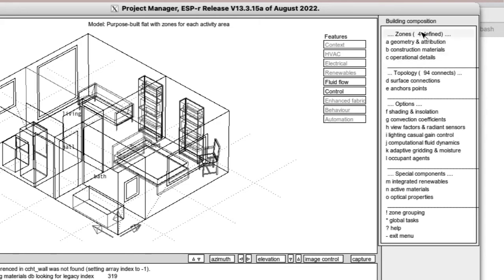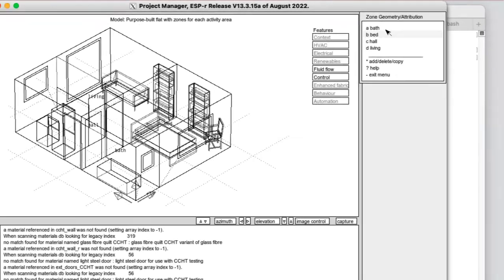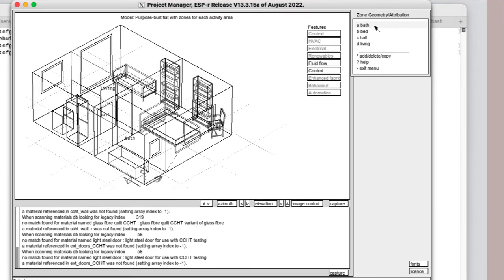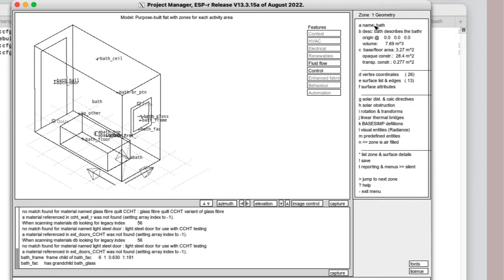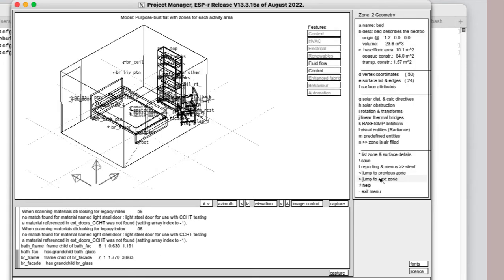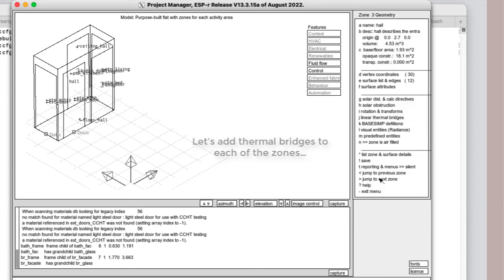The usual suspects for thermal bridges are where the concrete floor structure meets the facade, where internal partitions join the facade, at the perimeter of windows and door architraves. ESP-r includes a number of rules that it uses to evaluate the edges of the surfaces in the model: topology, boundary conditions, composition, and orientation.